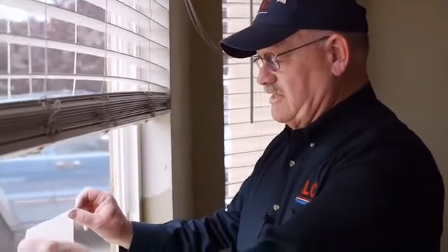Another thing you can do to ensure that your swamp cooler is operating at top efficiency is to be sure that you have plenty of relief air. As the swamp cooler forces cool, moist air into the house through the duct system, that air has to have a way to exit the house so that you have a fresh air exchange. One way to do this is to place a tissue on a window screen.